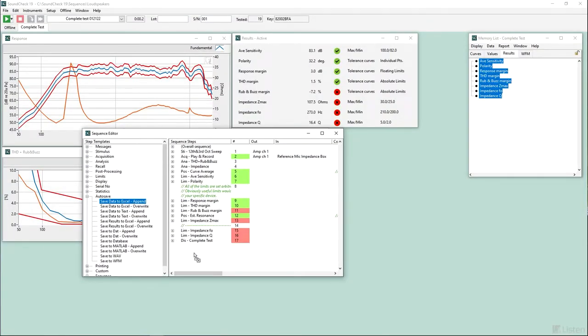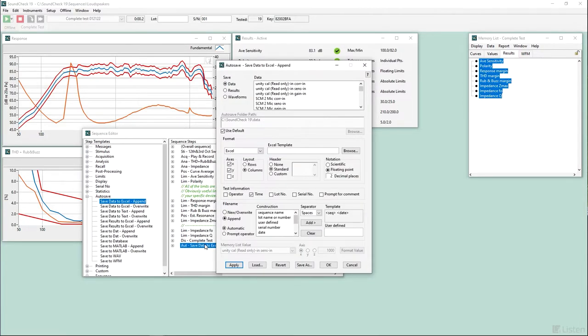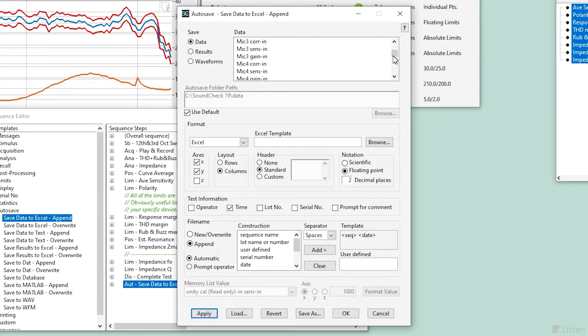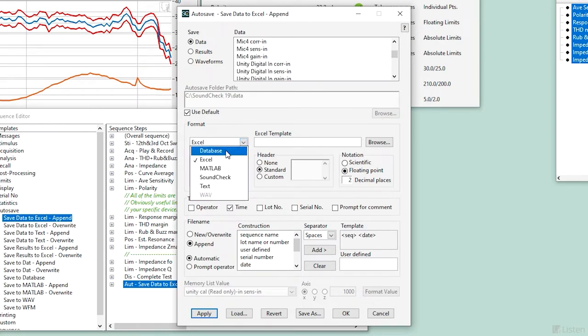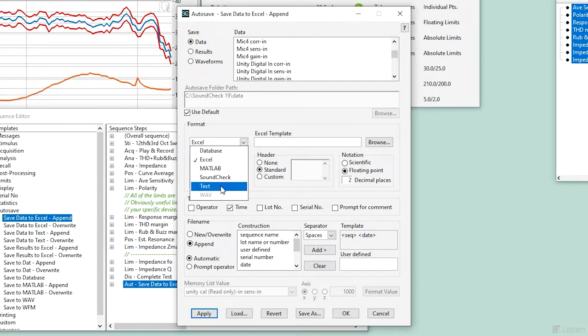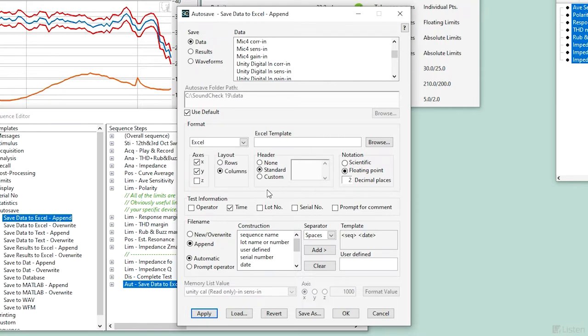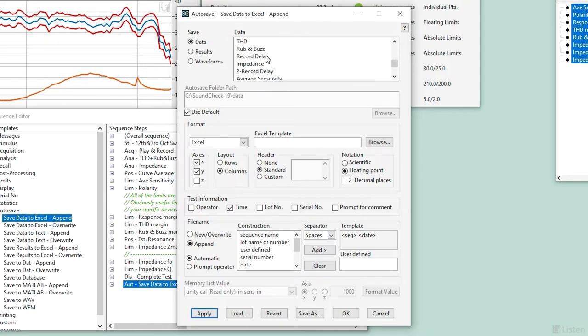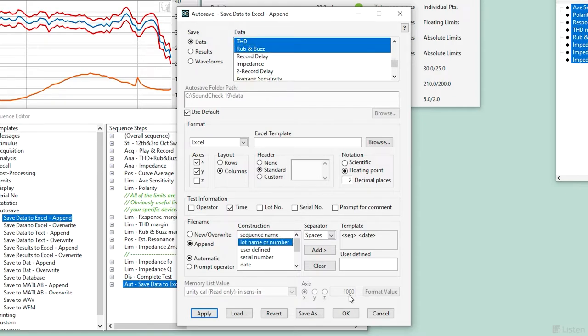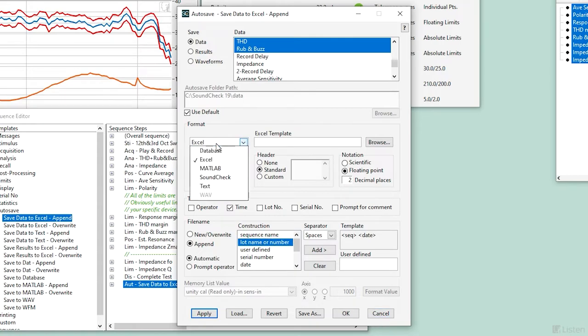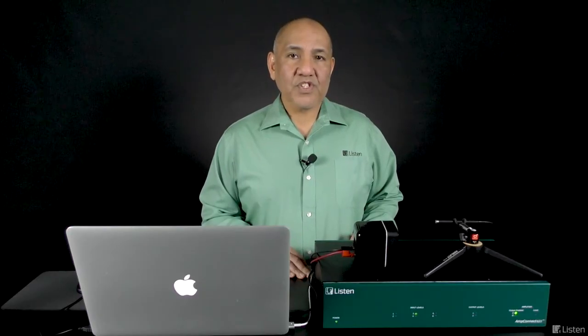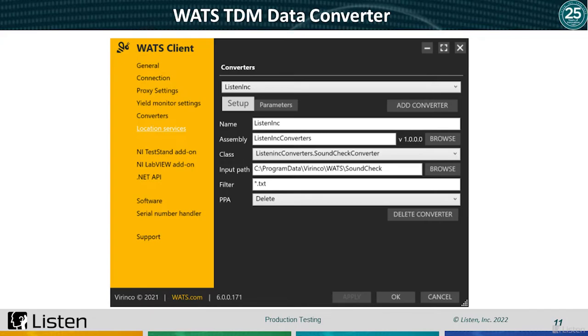If you're not familiar with SoundCheck, it's very easy to build sequences with drag and drop. I'm going to add an autosave step to the sequence. The autosave step allows you to select data organized by type on the left and choose the format of the saved data. From the drop list, you can see a list of data types including Excel, MATLAB, SoundCheck native file format, and text. Using append, we can keep a running file of each iteration of your test run. For example, one Excel file versus a separate Excel file for each sequence run. You can also control the naming format of your autosave data. Most recently, we improved SoundCheck's autosave to database file format. And as a result, saving to database is faster and more efficient. If you're familiar with the WATS test data management software, we've recently developed a utility that will convert SoundCheck generated text files directly into WATS for further analytics and process management.